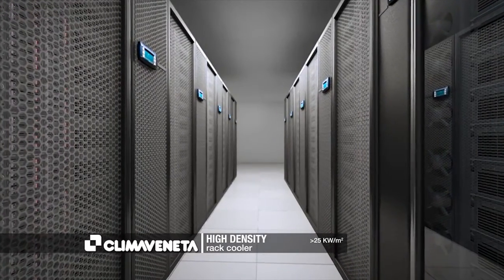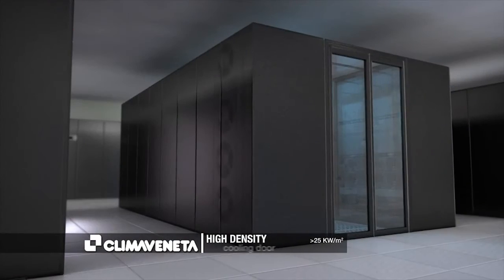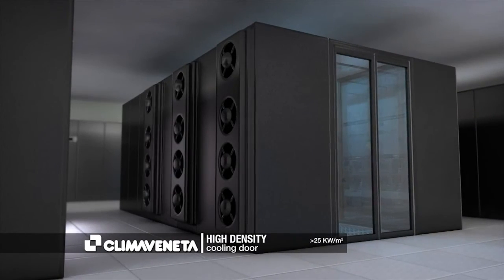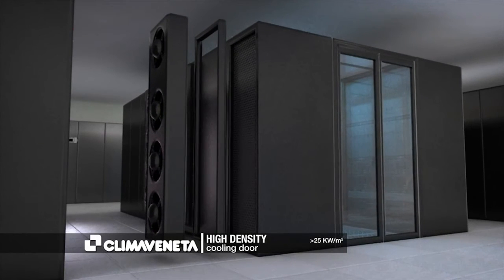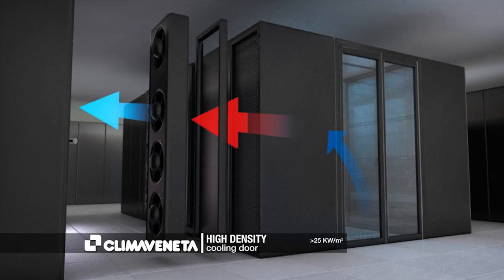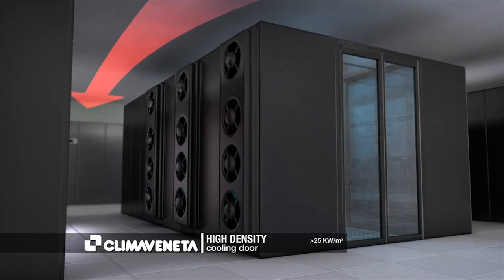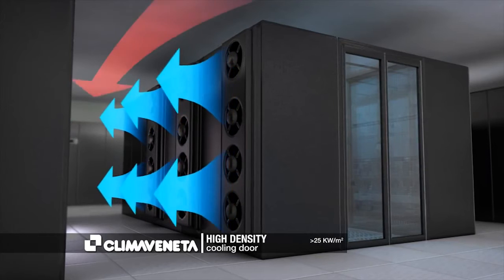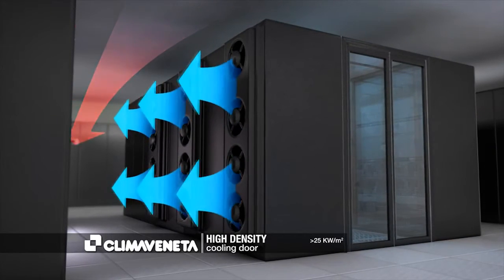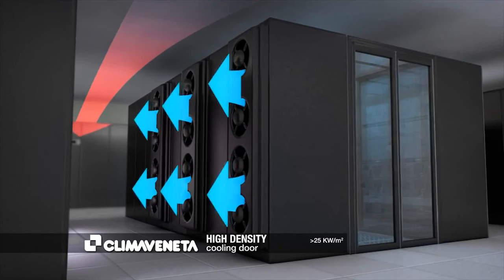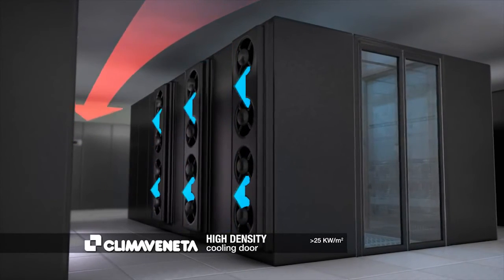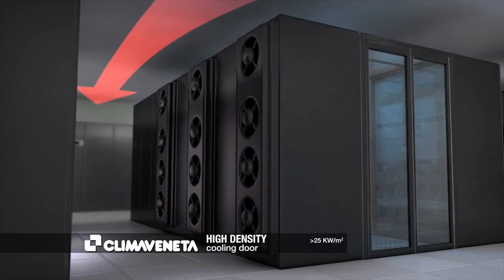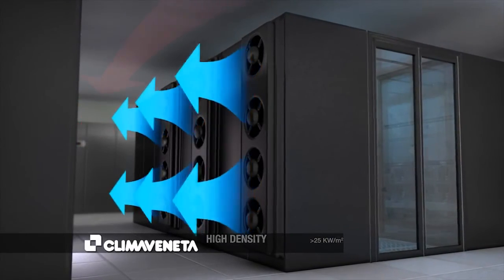Another solution is the cooling door. This device has been designed to be installed directly behind the server rack. The airflow, once heated from the servers, passes through the cooling coils of the back door, so that the cooling happens close to where the heat has been generated. What's more, the cooling door has electronically controlled fans to perfectly modulate the cooling capacity according to the actual heat load. Because the footprint of the door is minimal, these can easily provide an increase in the cooling power installed in the server rooms.